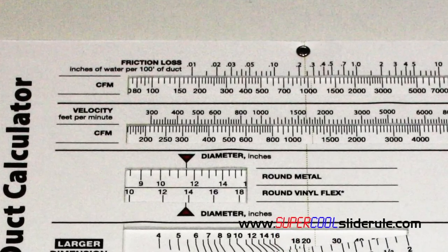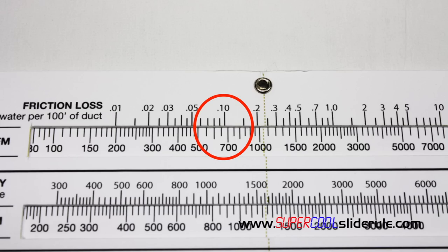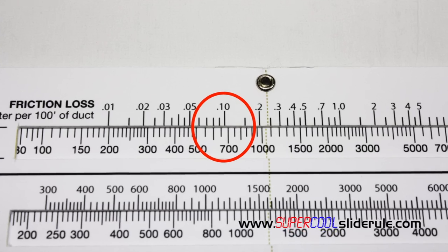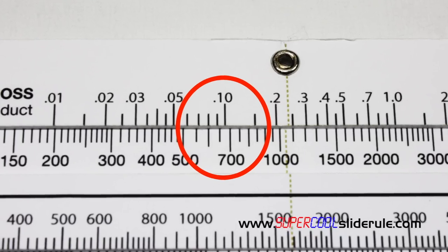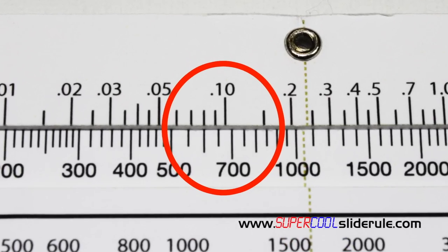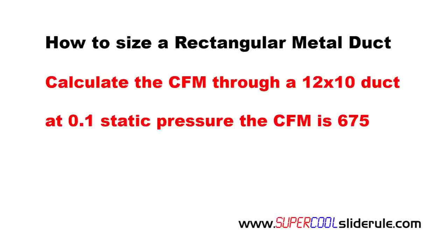Next we need to know what our desired static pressure is. In this example we will use 0.1 as our static pressure. I chose this number because this is a very popular static pressure for the supplier of many air conditioners in use today. We locate our static pressure of 0.1 right here. Directly under this number we will see 675. So our CFM through 12 by 10 duct at a 0.1 static pressure is 675.